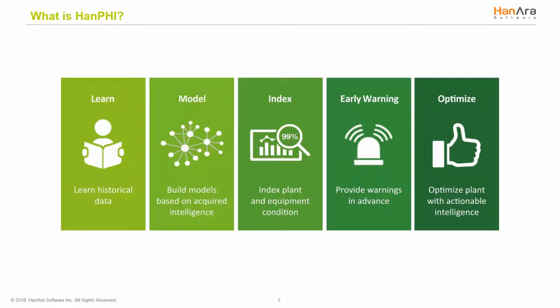At the core of this technology is its ability to detect several thousand unique patterns based on the historical plant data. These patterns let you understand what the current value of the tag is in relation to the operating condition. And the solution doesn't require a pattern for every single instance of every single condition. The solution uses its intelligence and algorithms to predict a pattern for conditions not contained in a set pattern.